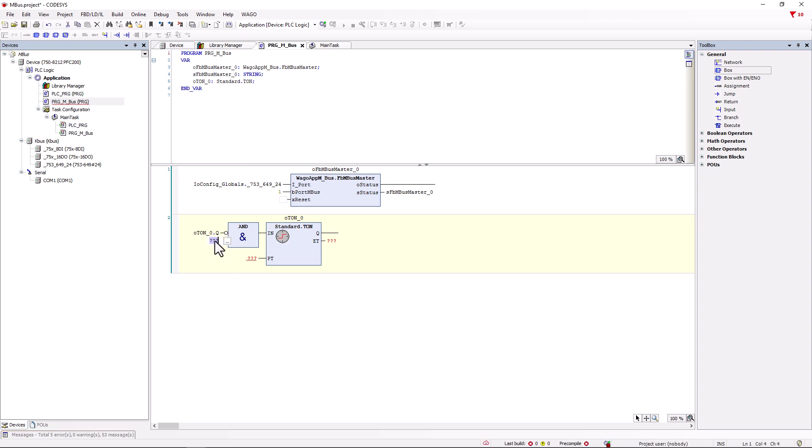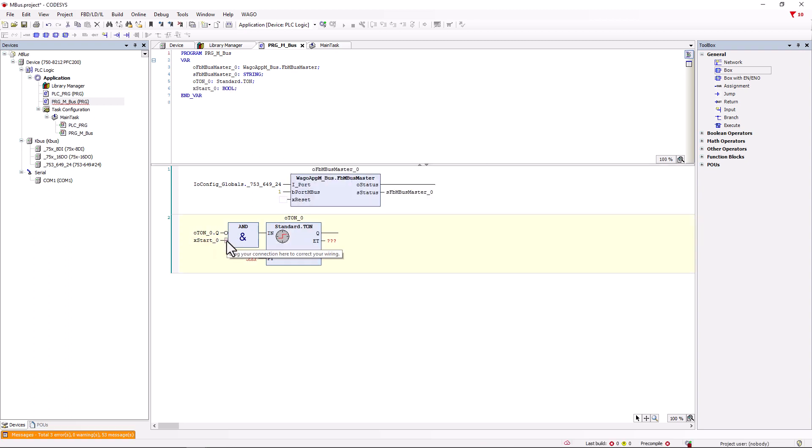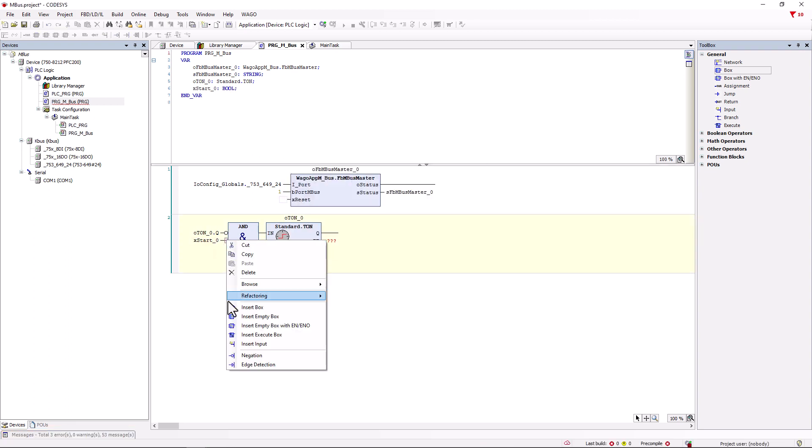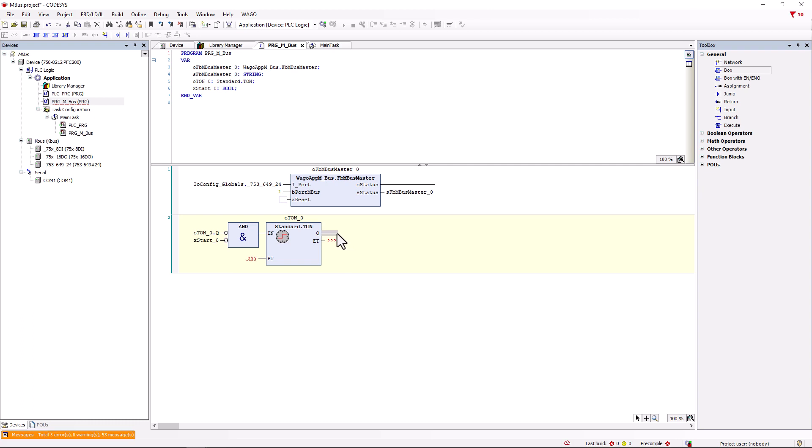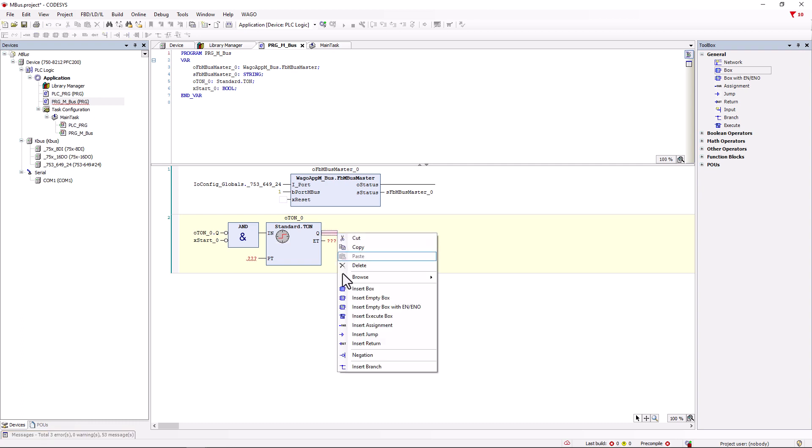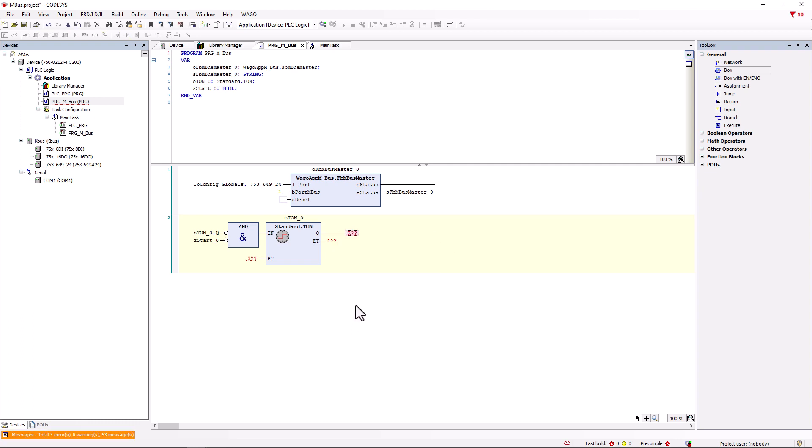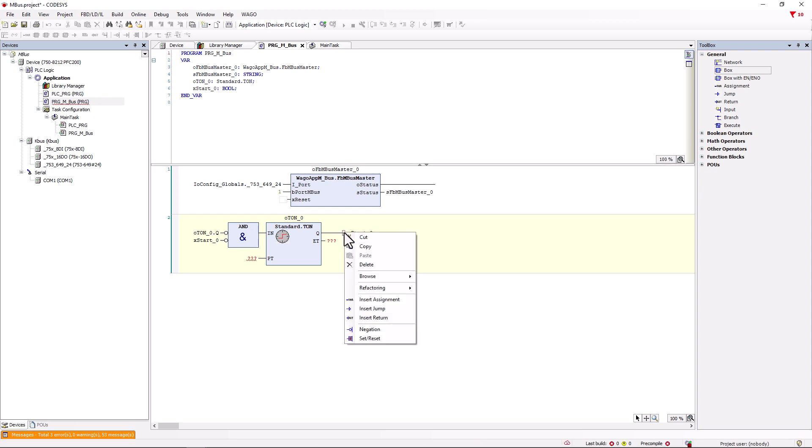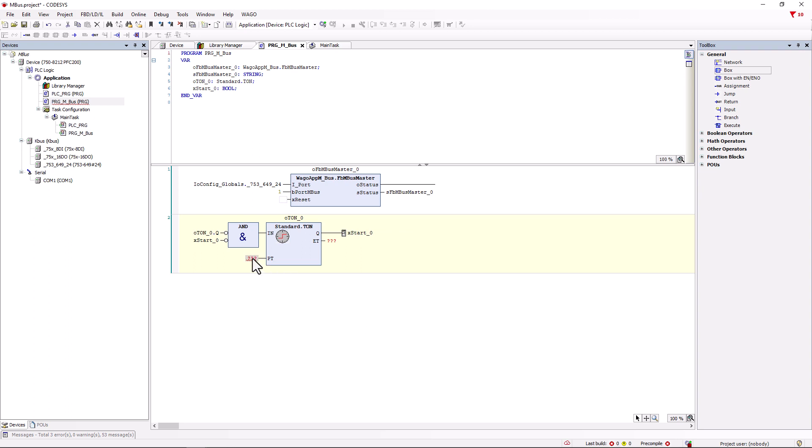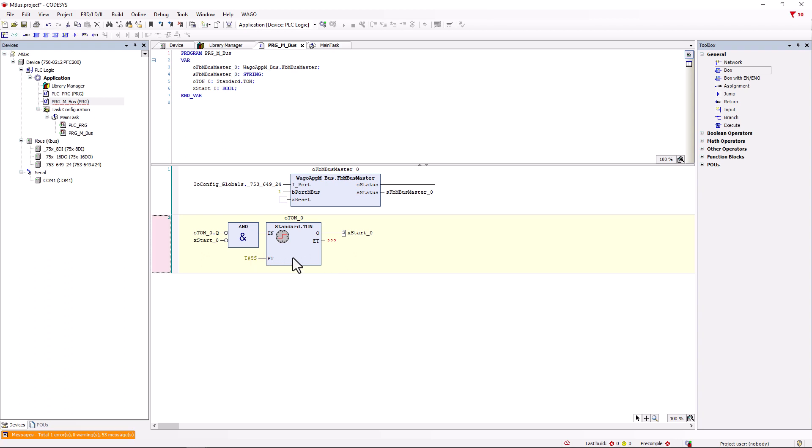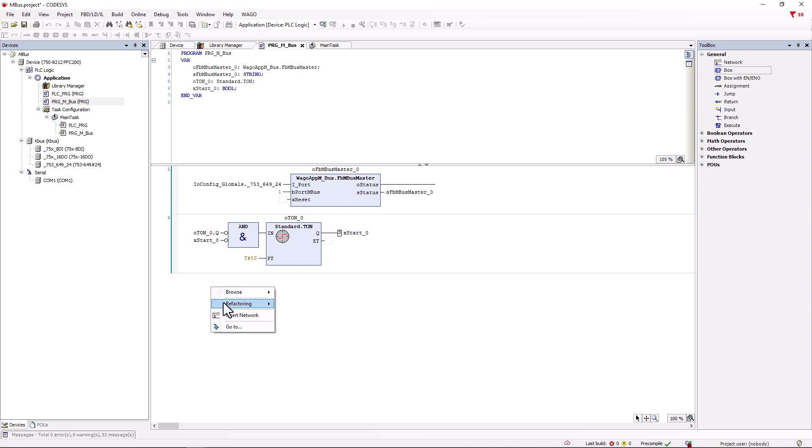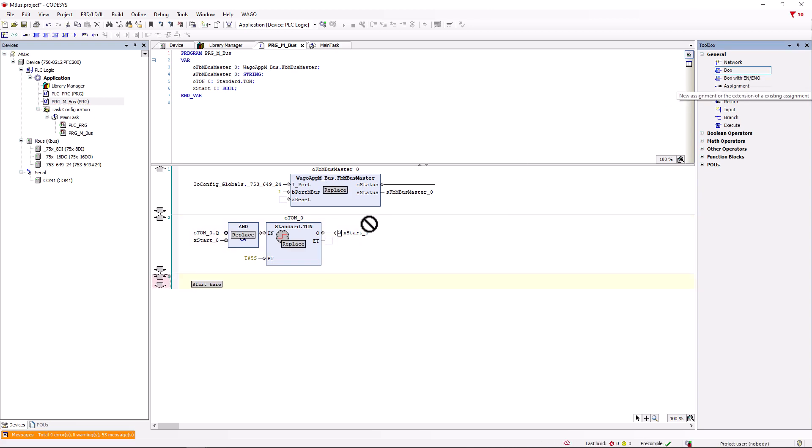We assign the variable xStart_0 to the second input of the AND gate. Have it declared and also negate this input. We assign exactly this variable xStart_0 to output Q, but we have to define it as set by right clicking directly in front of the variable. Now we give PT a time, in this example only of 5 seconds, to be able to show the function of the module. In practice, significantly longer times are common here, for example 15 minutes. In this example, we do not need the output ET, which is the elapsed time. This completes the TON function block and we add a new network.